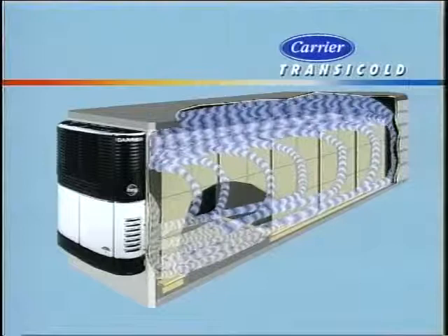The manual defrost key will initiate a defrost cycle once the box temperature is below 40 degrees. Pressing the manual defrost key once will put the unit into the defrost cycle. The unit also comes with an automatic defrost switch and defrost timer. If the box temperature is too warm for the unit to go into defrost, the message center will show "Cannot start defrost cycle." When the defrost cycle does start, the defrost light will come on, the box temperature will be replaced by letters DF, and defrost cycle started will appear in the message center for a few seconds, then change to status OK.